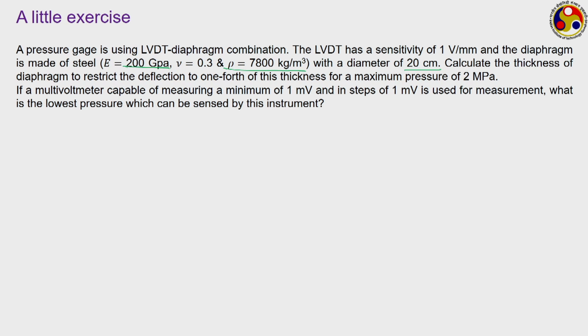Now we have to calculate the thickness of this diaphragm so that we can restrict the deflection to 1/4 of its thickness, for a maximum pressure of 2 megapascal. That is the maximum pressure we are trying to measure with this LVDT diaphragm combination, and we want to design the diaphragm with such a thickness that corresponding to this 2 megapascal, the expected maximum deflection of this diaphragm is restricted to 1/4 of the thickness of the diaphragm itself.